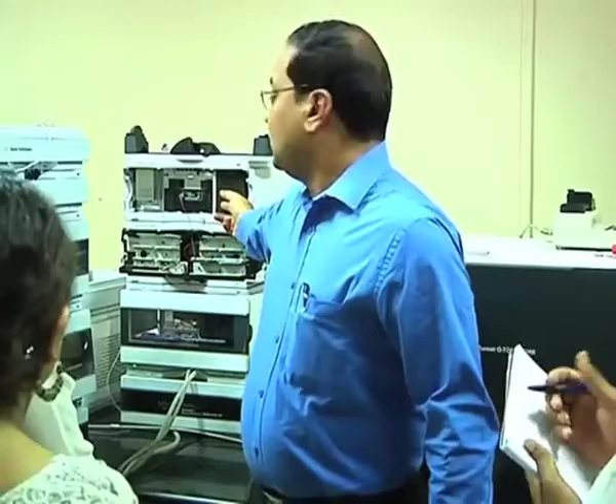And then there is the DAD, that means UV analysis. Typically there are two pumps, as I told you, in the pump configuration. Pump A consists of water with formic acid, and pump B consists of acetonitrile, typically with 0.1% formic acid. So why formic acid? To give protons. Why so? Because I know my analytes are peptides, which have many amide groups that can take protons and get charged. And I know the basis of mass spec is what? I need charge, mass to charge. Unless my analyte is ionized, the MS is blind. It cannot see. So the prerequisite of an MS analysis is that your analyte must get charged. In electrospray ionization, typically your analytes get ionized in solution, meaning in the solution itself it gets protonated, and ESI generally facilitates the ionization. It creates an environment where your ions move into the MS suitably.